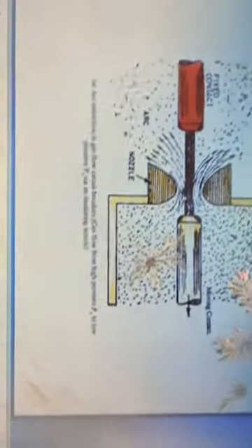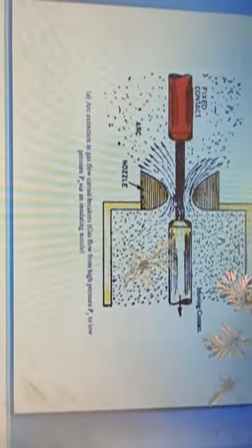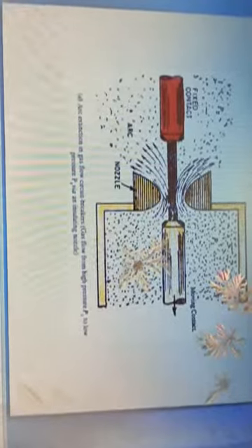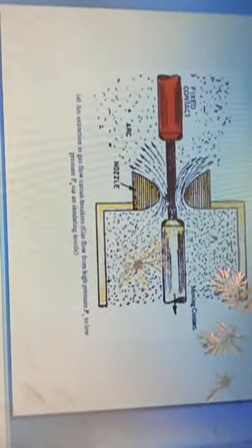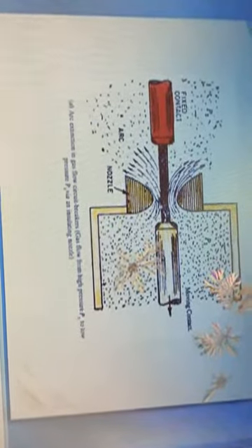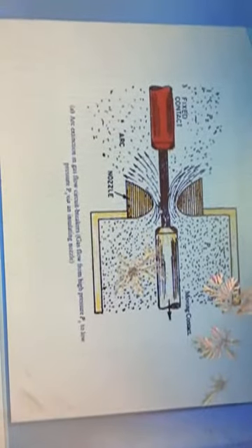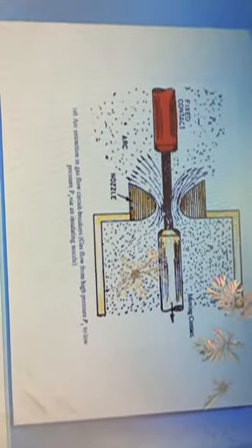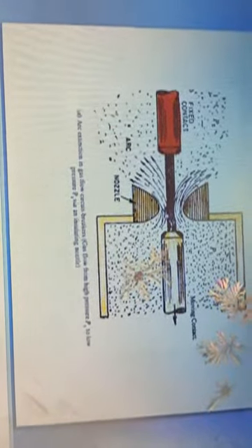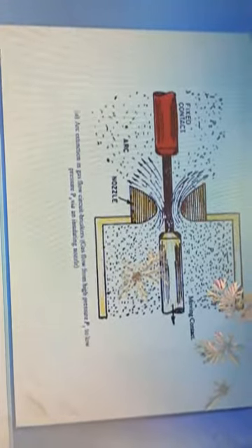In this, the moving cylinder is coupled with the movable conductor against a fixed piston, and there is relative movement between the two, and the gas is compressed in the cavity between the movable cylinder and fixed piston.